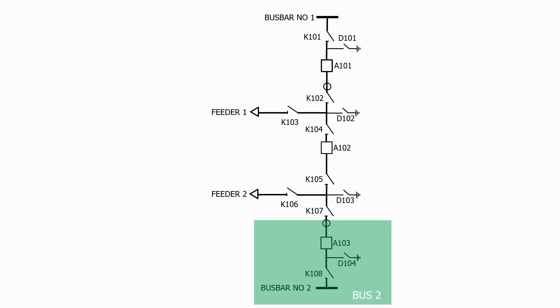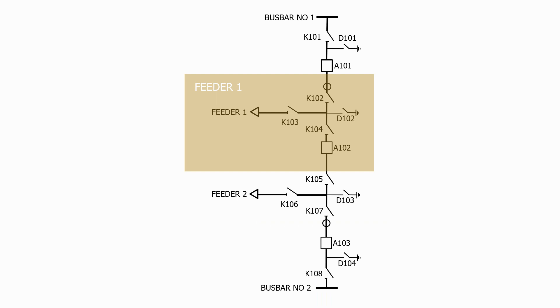What about the protection zone for feeder 1? Well, we know we need to overlap with the busbar number 1 protection zone, so let's place a current transformer here. There are two possible paths for the current to flow into the feeder, therefore we need a second current transformer to complete the protection zone, so let's place a current transformer here.